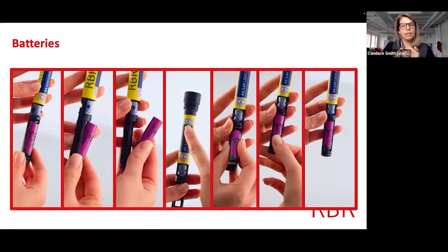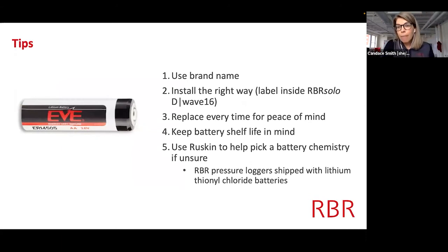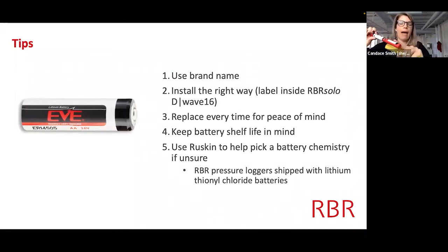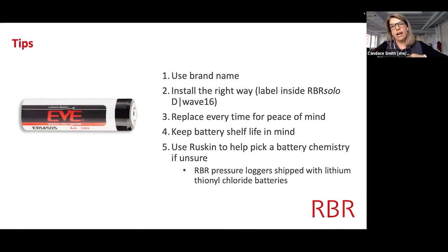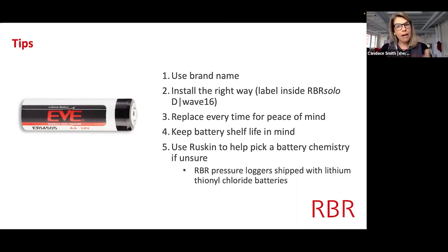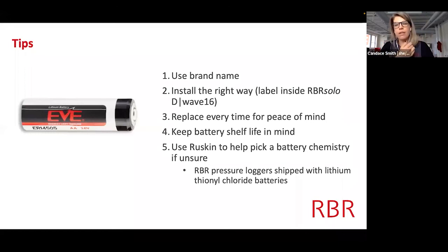The last consumable is the battery. There's one AA battery inside the Solo-D Wave 16 — really easy to pop out and pop a new one in. Make sure you're using a brand-name battery and install it the right way — there's a label on the back panel showing direction. I recommend replacing the battery every single time, just for peace of mind. Even if Ruskin tells you you have six months and you deployed for three months, the cost of losing that data is much greater than one AA battery. Keep battery shelf life in mind — check expiry dates. The battery we currently ship with is an EVE lithium thionyl chloride battery.